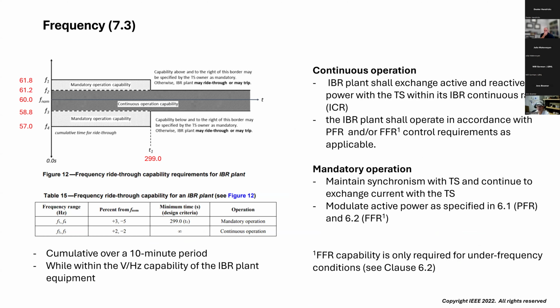So finally, that was probably the majority of the detail in this section. There are also frequency ride through requirements in clause 7.3. This is the table here. They're all based on whatever the nominal frequency is, so I've superimposed what it looks like for a 60 hertz system here in red. The key thing is this is cumulative over a 10-minute window, and there are some exceptions for volts per hertz capability of the IBR plant equipment. This really goes back to, you have type 3 wind that's directly connected to the AC system. You have transformers, etc., that may have volts per hertz limitations. So the standard's not requiring you to exceed that of normal equipment design standards.